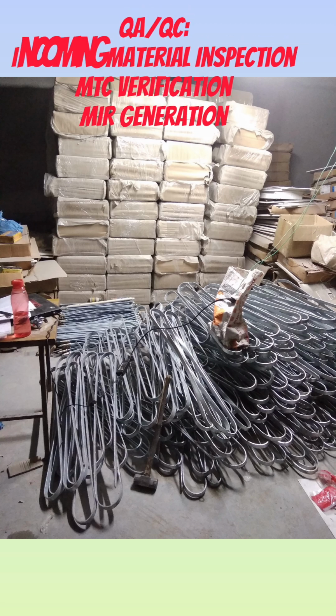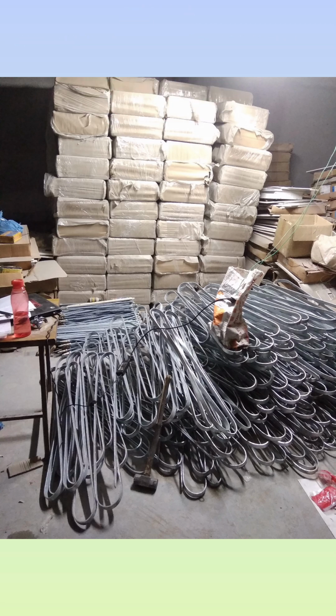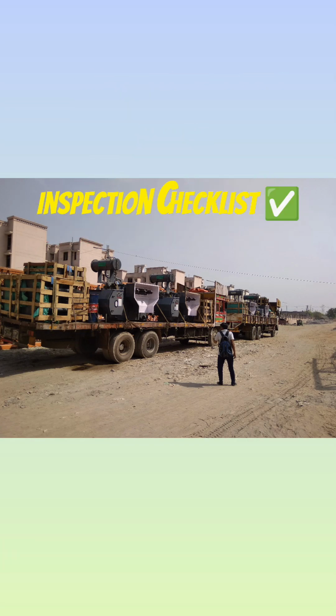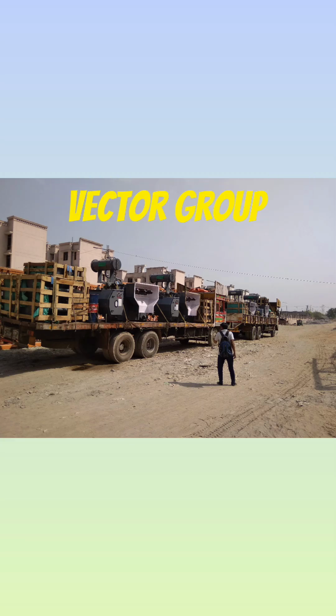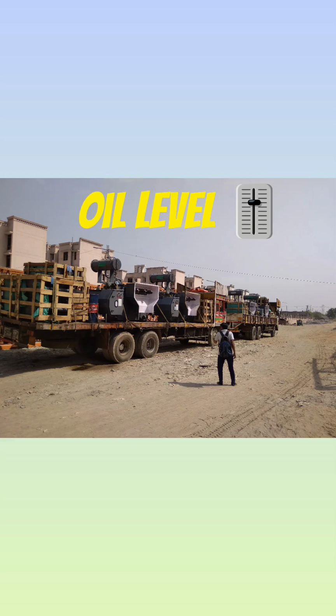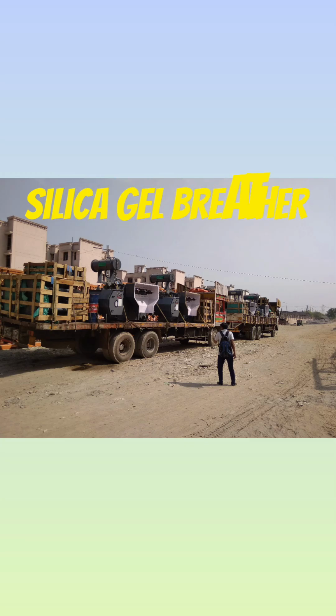Here, 1600 kVA transformers are being received. The inspection checklist includes verification of nameplate data, vector group, oil level, silica gel breather condition, and absence of transit damage.